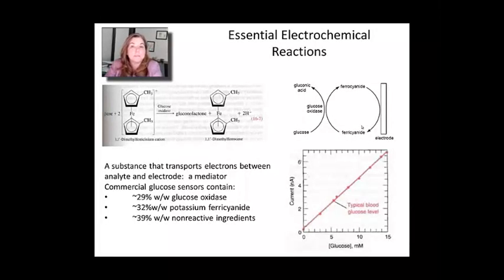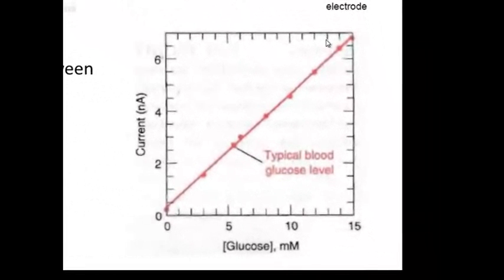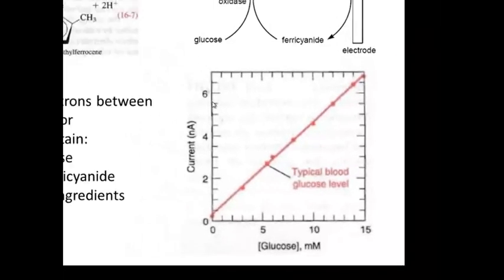This glucose to gluconic acid reaction is coupled to the ferricyanide couple, called a mediator. A mediator is a substance that allows you to measure what's going on in one reaction and translate that into an electrical signal. Shown here is an amperometric measurement where glucose concentration relates to current generated in this couple.